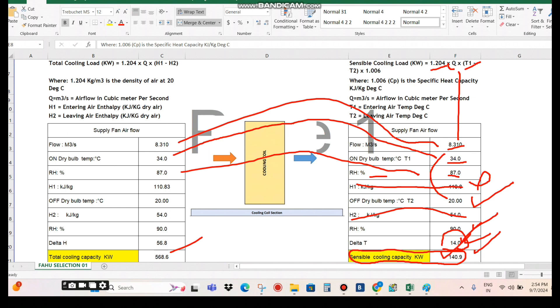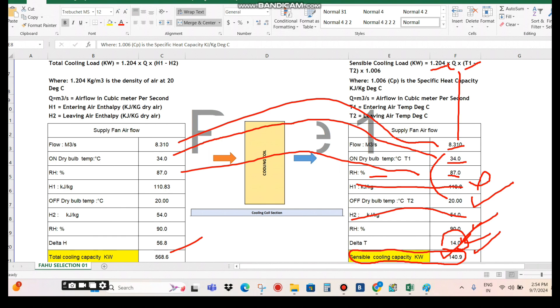I hope you are now clear on how to decide the on-coil and off-coil conditions and why we select the monsoon/worst condition — 34/87 — for the FAHU, even though Dubai Building Regulation specifies 46/29 for general air conditioning design. For the FAHU, since we take fresh air from outside, we must follow the country's worst humidity condition. In future videos I will explain in detail the pre-cool coil, reheat, and heat recovery wheel concepts for FAHU. Thank you for watching.